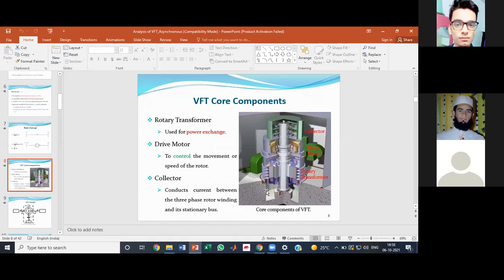Question: what is the efficiency of the VFT? It's a very good question. The efficiency claimed by General Electric Company is 99.9%, since it is a transformer. But if you analyze the VFT, as I was telling you, it's a separate device in which the drive motor, collector bus, and rotary transformer are all on the same shaft. They have managed the air gap and all those things, so their efficiency is very high. But if you use a wound rotor induction machine mechanically coupled with a DC drive motor, the efficiency will come out to be less than that.